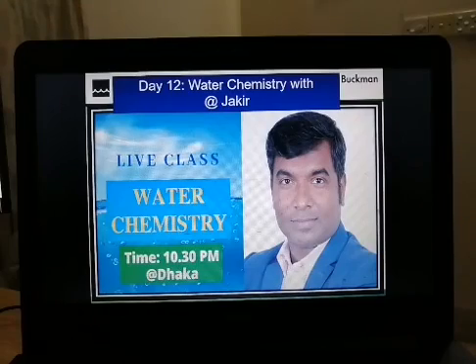Mominul. Nice question. Arif Iqbal asks: if the feed tank has a deaerator, is it necessary to use an oxygen scavenger? Arif, thank you very much. Very important question. And the answer is yes.